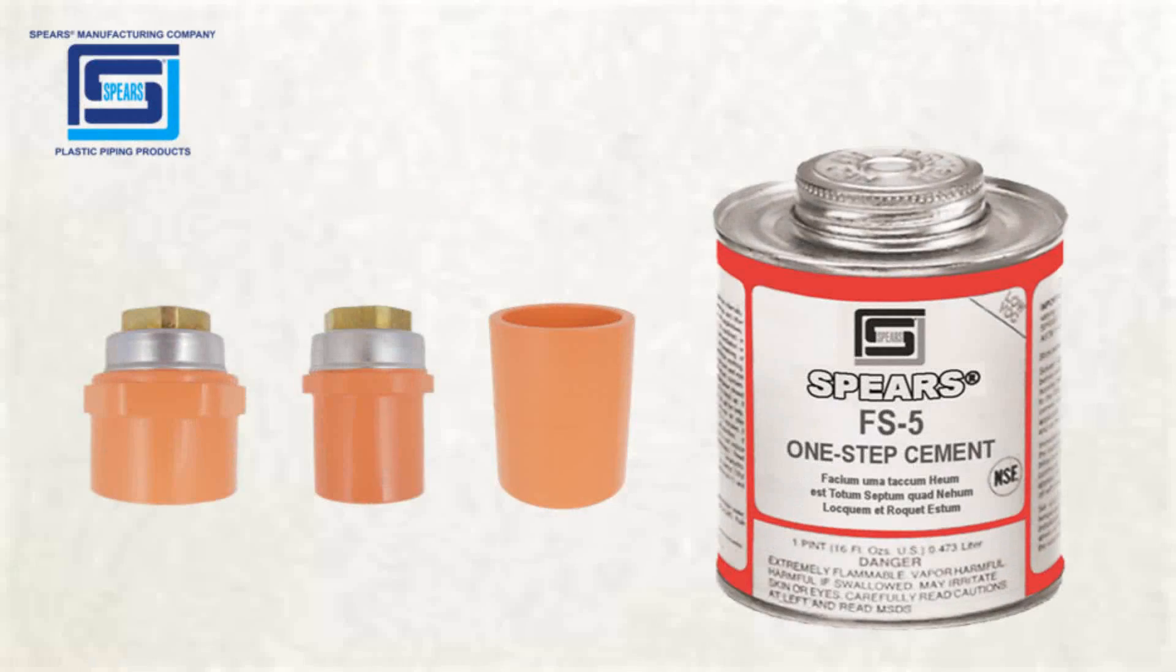For this demonstration we will be removing a Spears Torque Safe Sprinkler Head Adapter and replacing it with a Spears Torque Safe Spigot Sprinkler Head Adapter and a Spears 1 inch fire sprinkler coupling. We will also be using Spears FS-5 one step solvent cement.